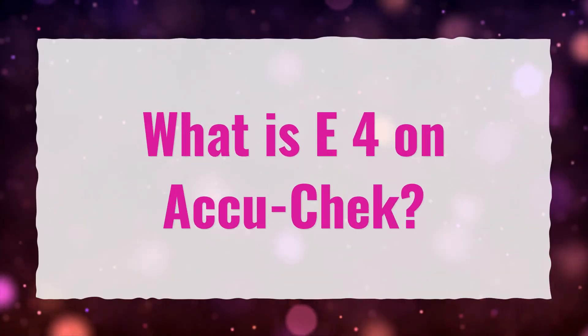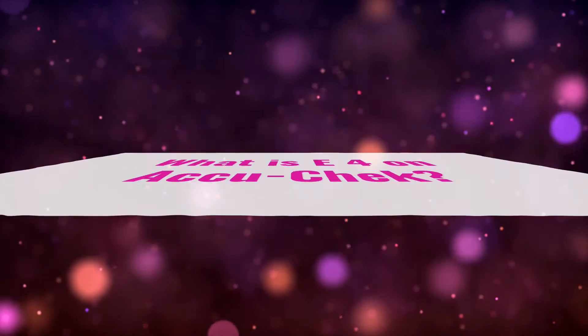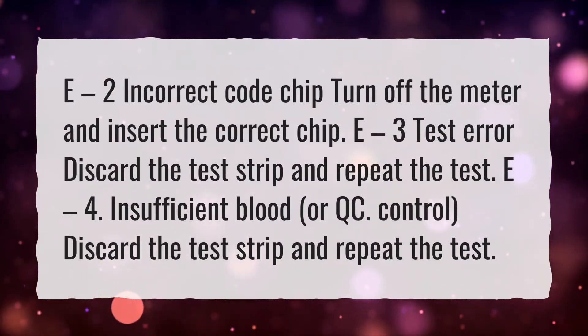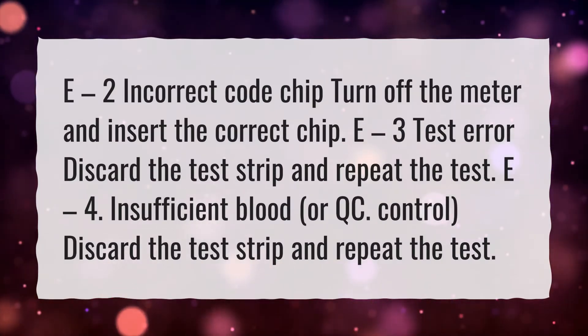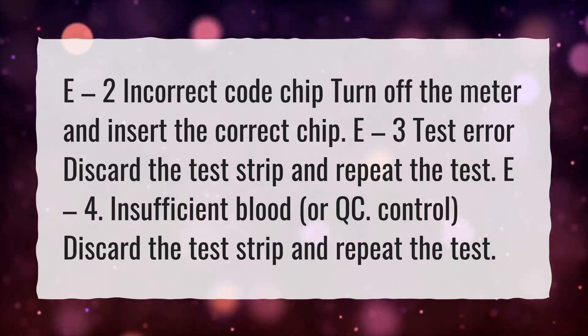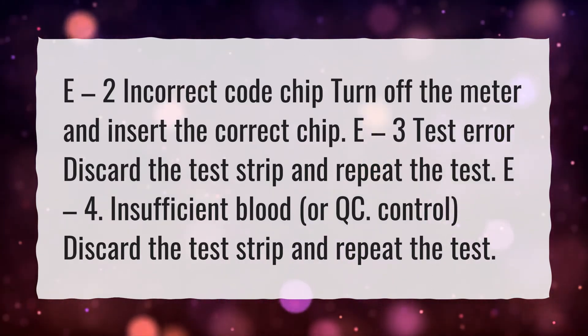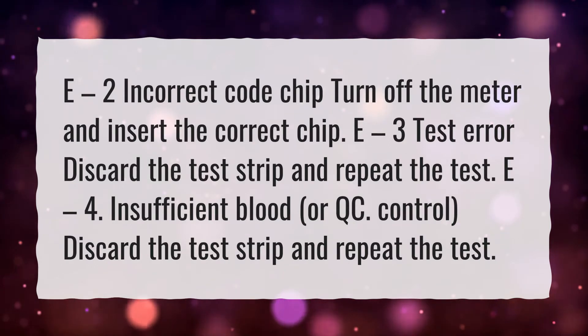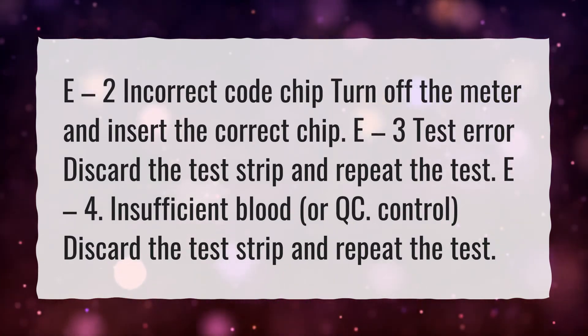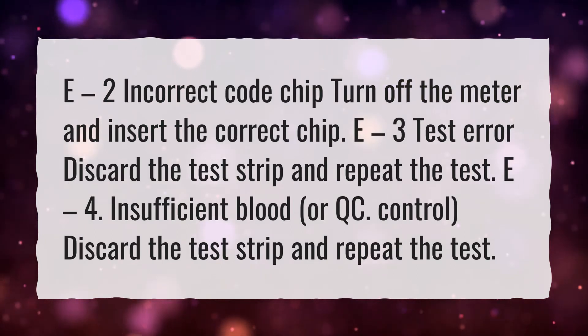What is E4 on AccuCheck? E2: incorrect code chip — turn off the meter and insert the correct chip. E3: test error — discard the test strip and repeat the test. E4: insufficient blood or QC control — discard the test strip and repeat the test.